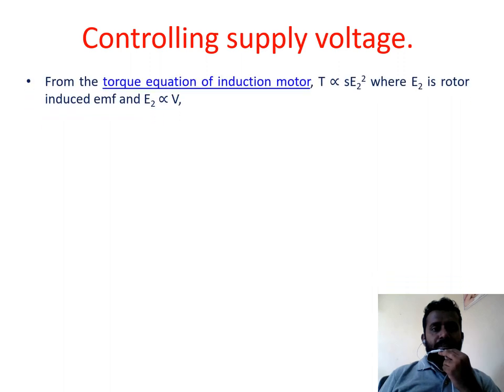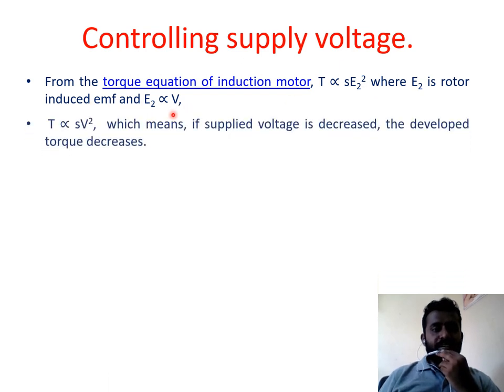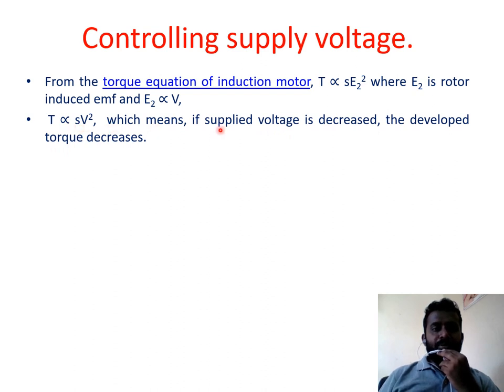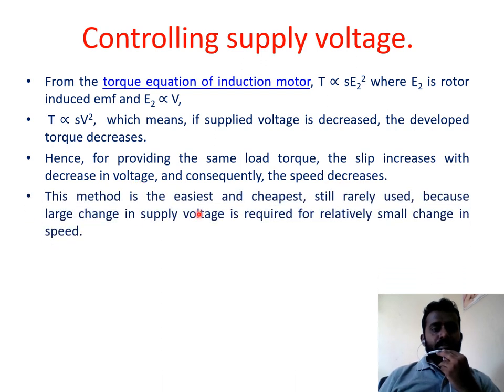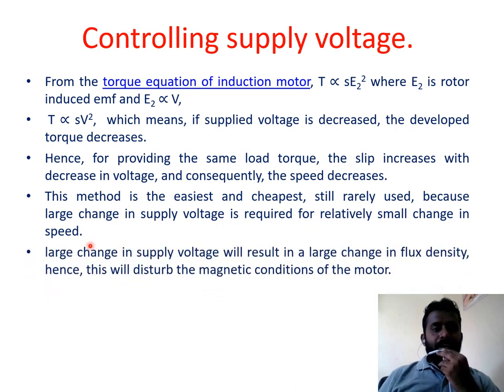Control supply voltage method: from the torque equation, T is proportional to S × E₂², and since E2 is proportional to voltage V, T is proportional to S × V². If supply voltage decreases, torque decreases. To supply the same load torque, slip increases, and consequently speed decreases. This method is the easiest and cheapest, but rarely used because a large change in supply voltage is required for a relatively small change in speed, which disturbs the magnetic conditions of the motor.